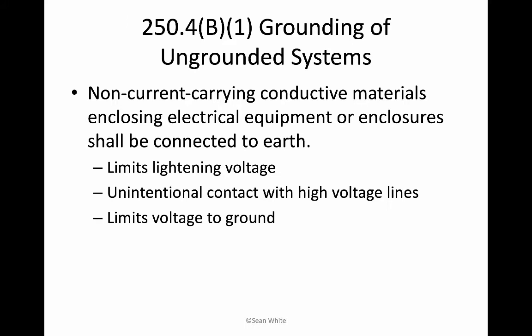But let's talk about what an ungrounded system might be. Sometimes a big building might have some voltage coming to it, and we'll say 480 delta ungrounded. Some big factory might have something like that coming to it. Some big factories could have more than 480 coming to them if you're talking about a giant factory. So you have a factory and it's got 480 delta ungrounded coming to it. That would be ungrounded. Just because something is ungrounded doesn't mean that you don't bond all the metal and things together. So you're going to bond everything together.